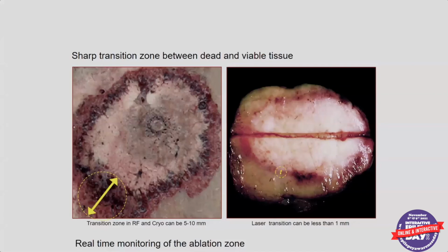And this particular type of destruction creates a very sharp boundary where tissue is destroyed. This is just outside the scanner on a piece of meat, where the destruction produced by the laser is very sharply contoured and normal tissue around it is relatively spared. And this is different from another technique that has been historically used for destruction of these lesions by passing electricity, or what we call radio frequency lesions, through the same electrodes used to pinpoint where the seizures are coming from. That technique, also effective, produces a much less predictable damage map, one that has broader boundaries of areas that are damaged but not necessarily destroyed.